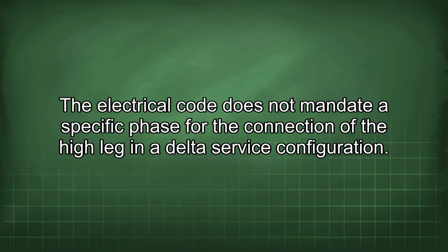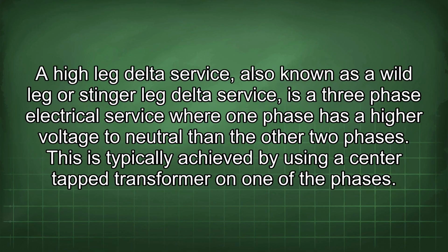The electrical code does not mandate a specific phase for the connection of the high leg in a delta service configuration. A high leg delta service, also known as a wild leg or stinger leg delta service, is a three-phase electrical service where one phase has a higher voltage to neutral than the other two phases. This is typically achieved by using a center tap transformer on one of the phases.